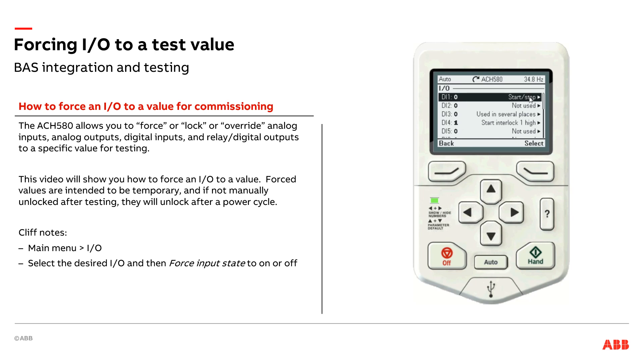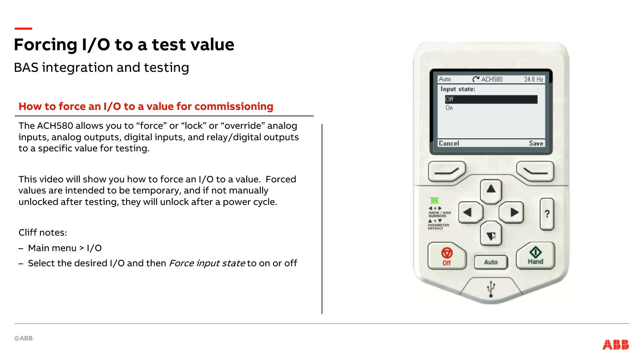Digital input 1 is programmed for start/stop. What I want to do is force that to be on. So I'm going to come in here, select the box for forced input state, and edit that. Behind me I have a demo case I just turned on — it's in auto mode. With an auto speed command of 34 hertz right now, it is now running.